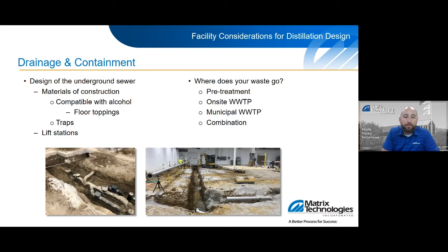And also for the drains, look at traps. I've gone both ways with this before. Traps are good in that they prevent the vapors from coming back up into the drains. If you think back to a few slides ago where we showed the low points where the vapors will collect, the trap will help prevent that kind of escaping from that area, but you can also consider free draining this to an isolated location so you're not trapping alcohol either.